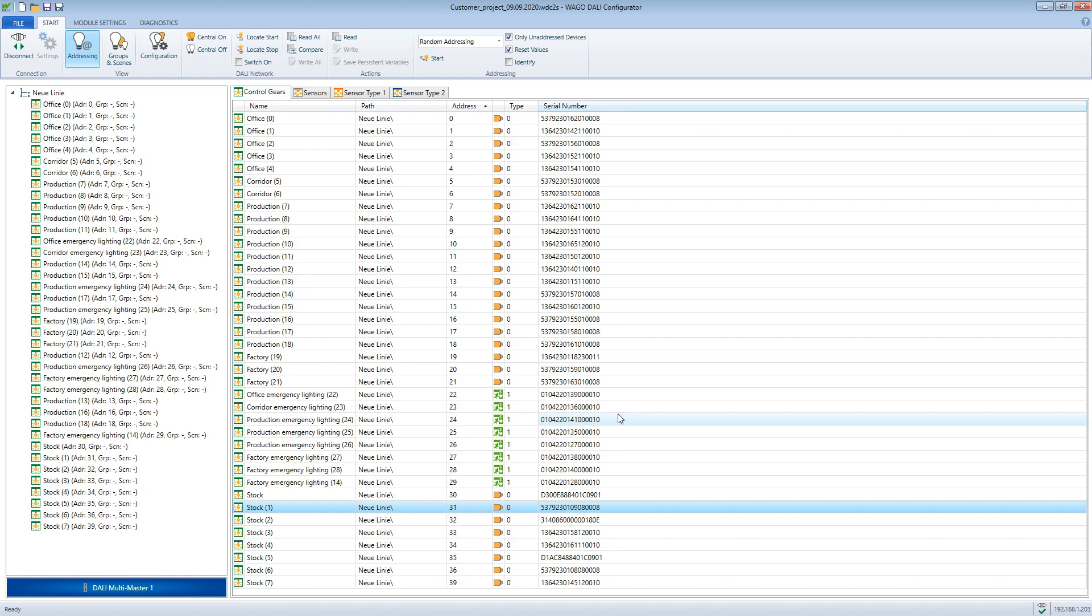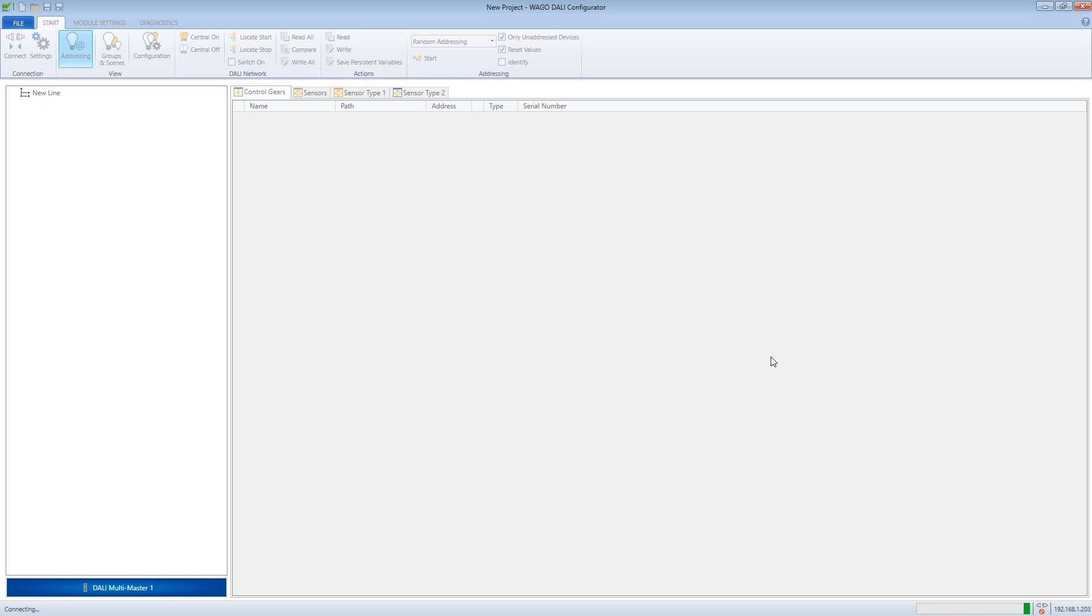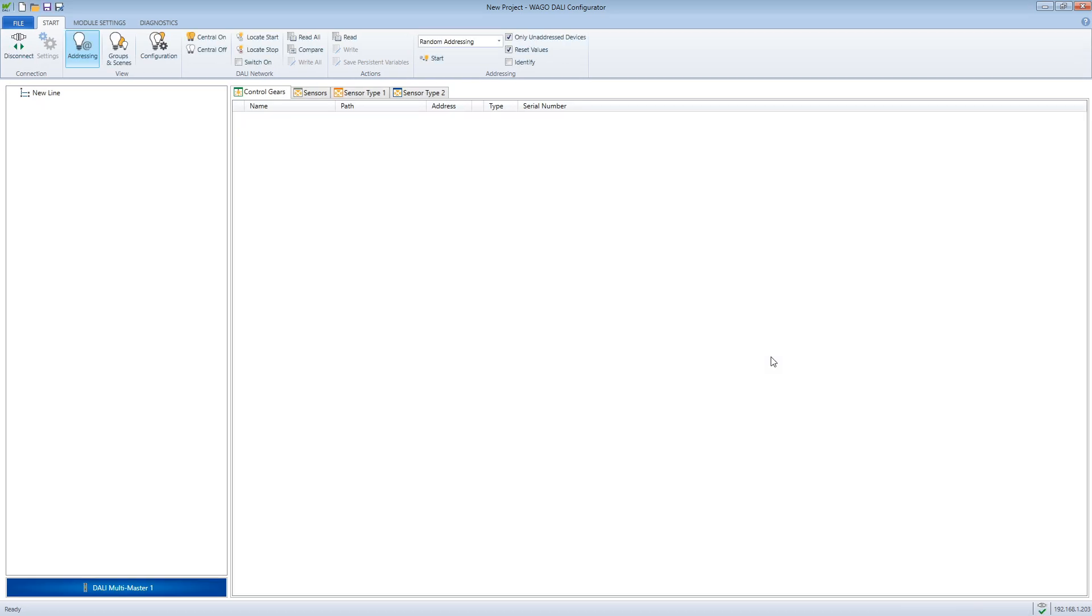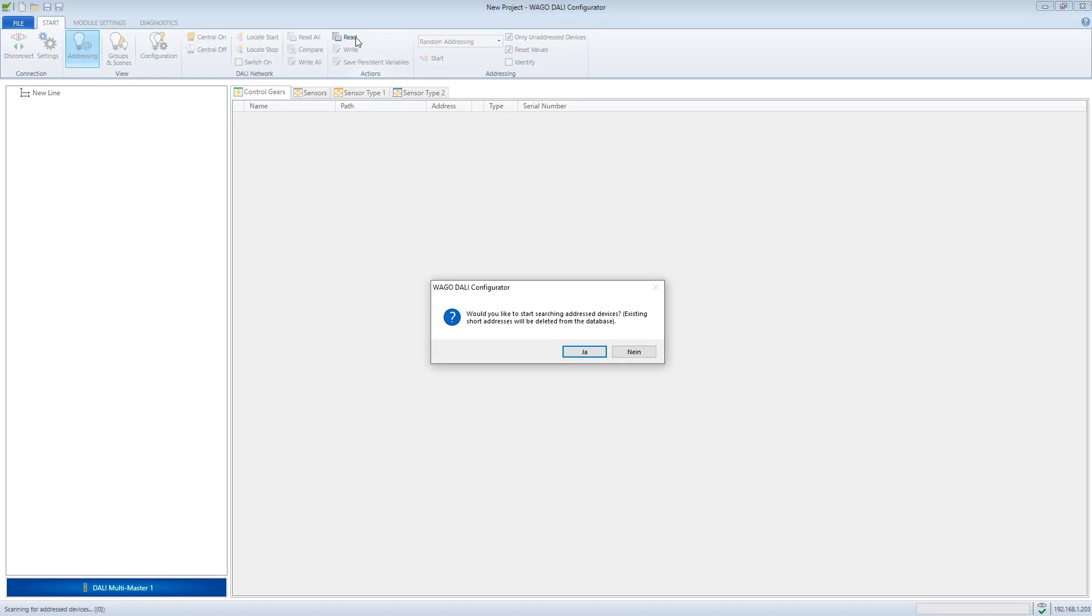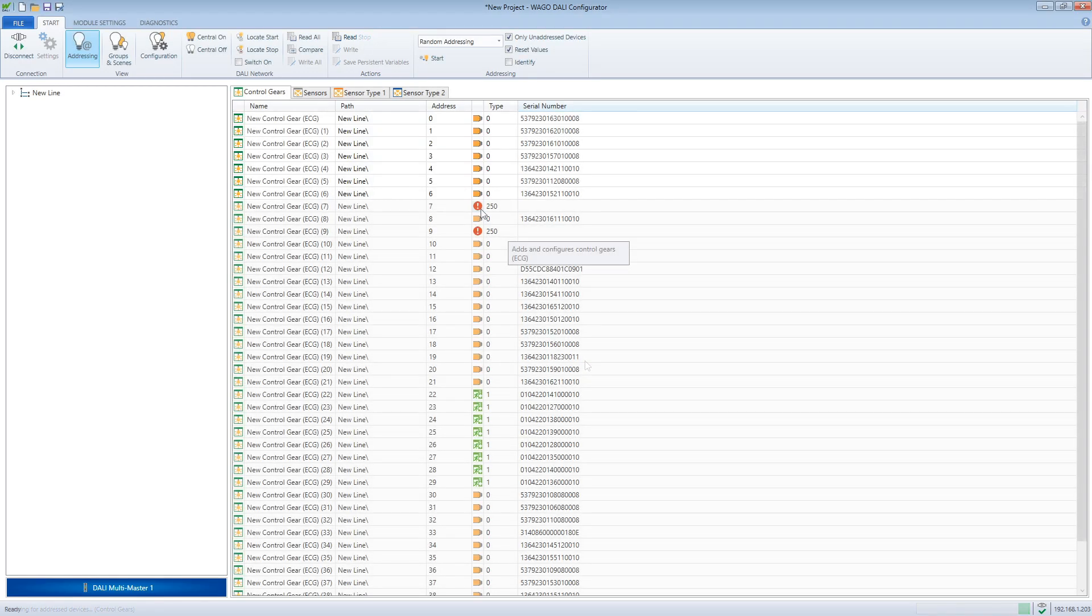We open another instance of the DALI configurator to not overwrite the configuration of the original project file. Now we connect to the corresponding module and read it out. In our case only control gears are installed. We select this tab and click on read. This will read out all control gears on the bus.